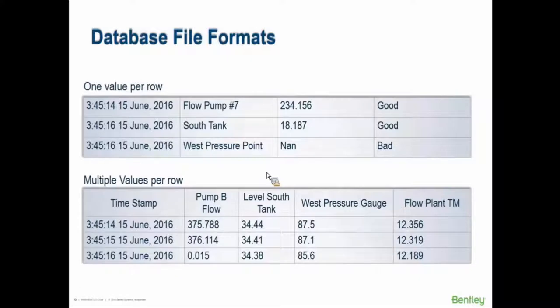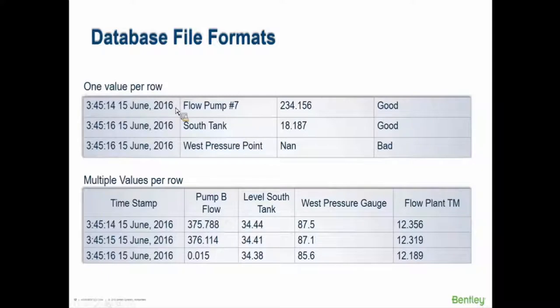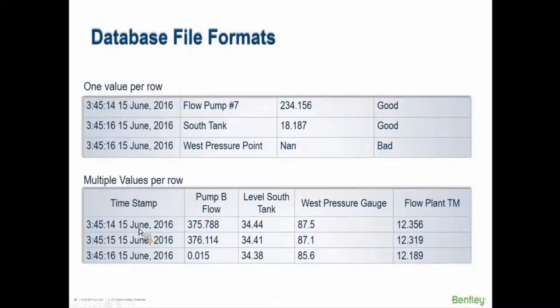What form can the data be in? There are a number of file formats as well as direct connection to the OPC server. One format is: for every row in the table you have a timestamp, the name of the tag in the SCADA system, the value, and optionally a quality index of whether the SCADA system considers it a good or bad data point — one value per row. The other format we accept is multiple values per row, which is common when data is exported to Excel: a timestamp column, labels for what signals these are, and numerical values in the corresponding row.